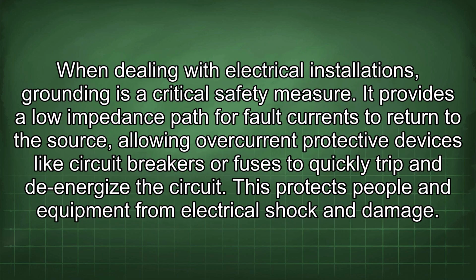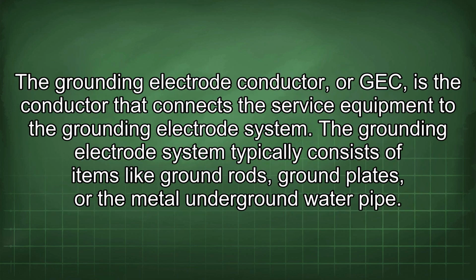When dealing with electrical installations, grounding is a critical safety measure. It provides a low impedance path for fault currents to return to the source, allowing overcurrent protective devices like circuit breakers or fuses to quickly trip and de-energize the circuit. This protects people and equipment from electrical shock and damage. The grounding electrode conductor, or GEC, is the conductor that connects the service equipment to the grounding electrode system. The grounding electrode system typically consists of items like ground rods, ground plates, or the metal underground water pipe.